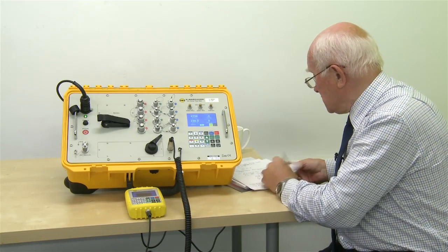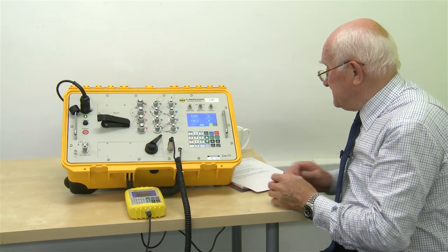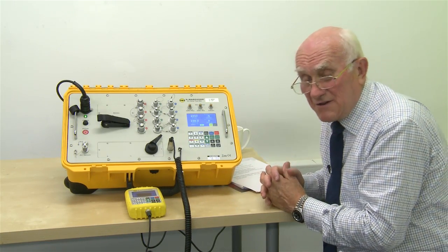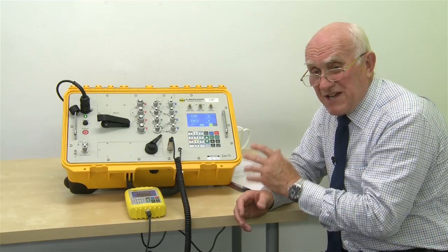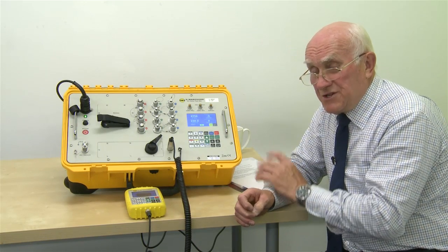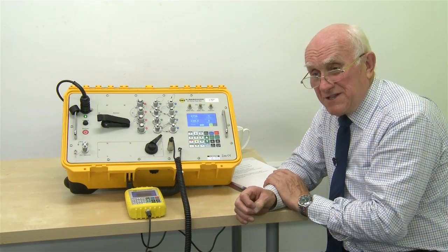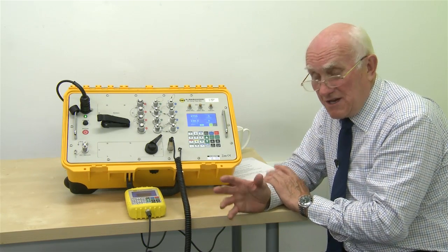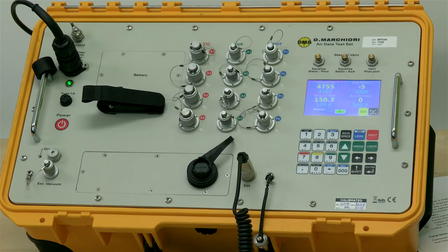I think I only now want to talk generally about some of the points I've already missed. The instrument has the ability to do programming. You can actually in here go into the programming mode and set up multiple different programs which can be given a specific name. Each program can have as many as 26 steps, in other words A, B, C alphabet. You can look at the answers to all those steps here on the instrument, or you can download them via the USB port into a PC.